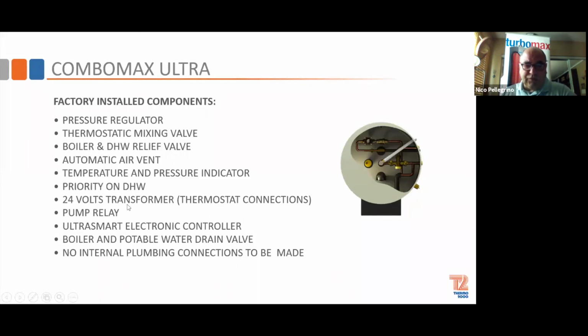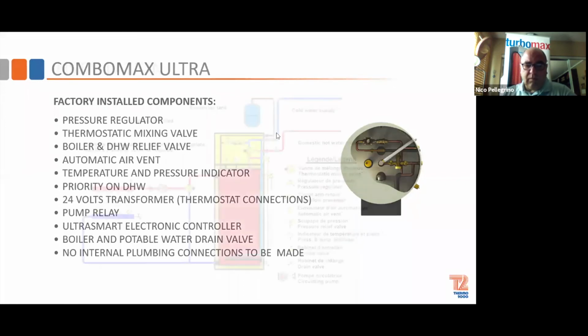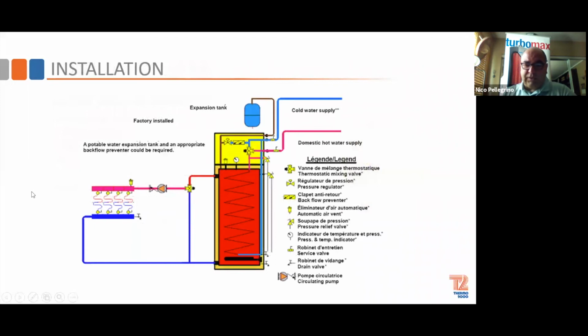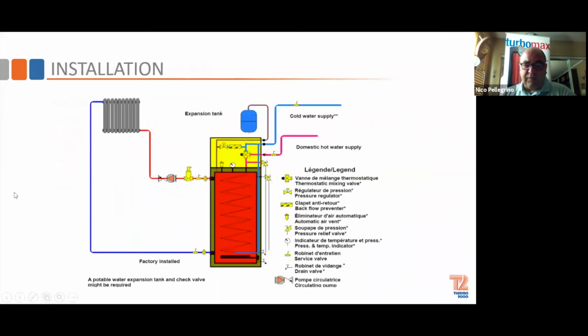And you also have domestic priority. So if you have it hooked up to a single pump to run an in-floor, somebody jumps in the shower and they're taking longer than 15 minutes, it will automatically turn that pump off and give priority to domestic. So this is basically showing you a quick drawing of what it would be like.